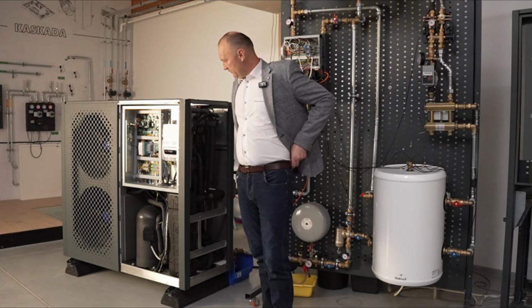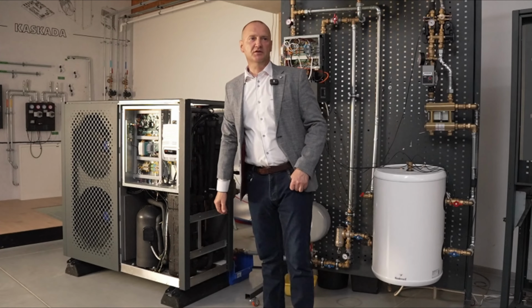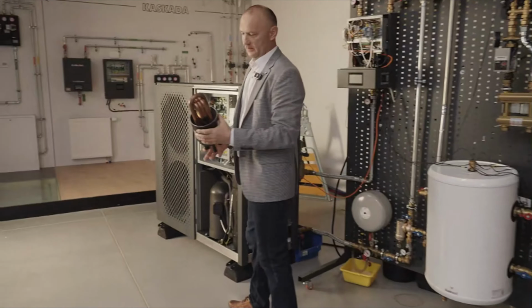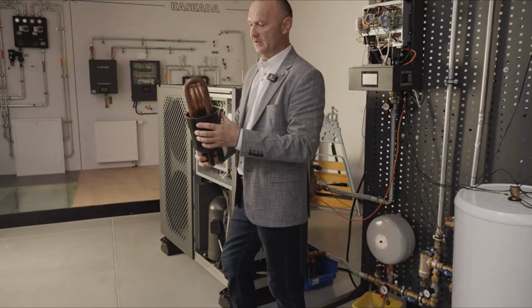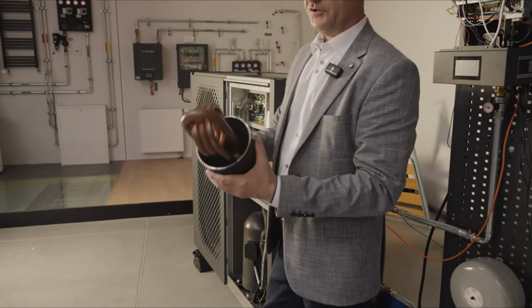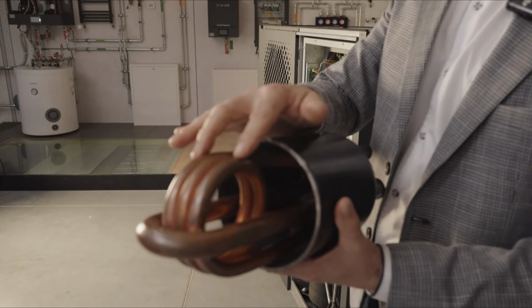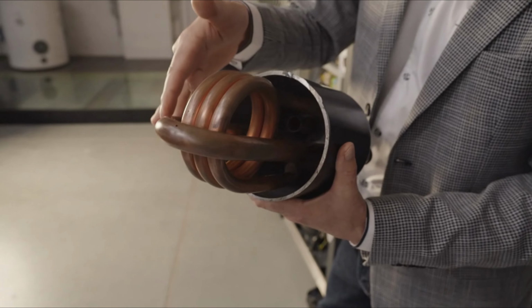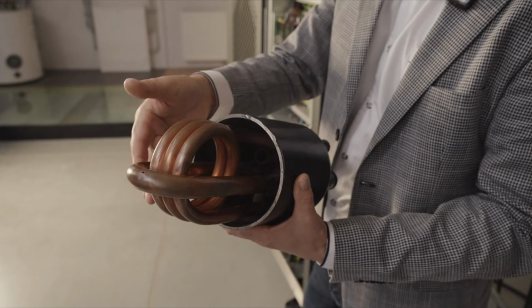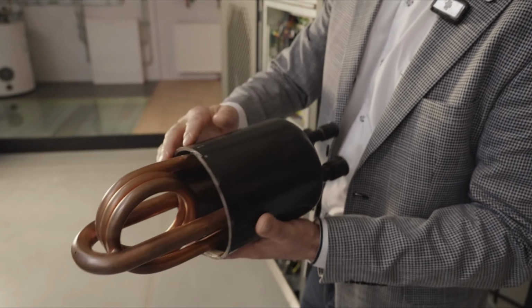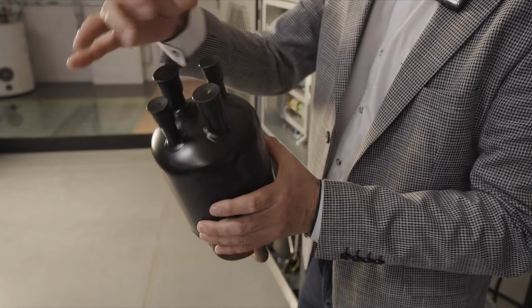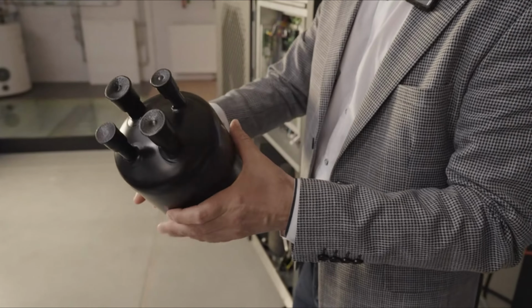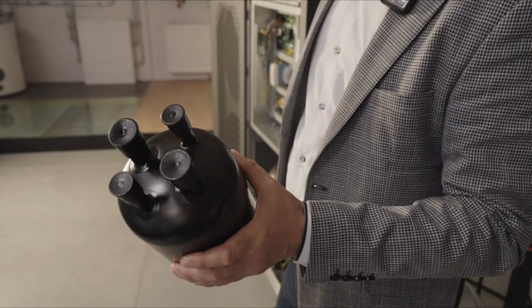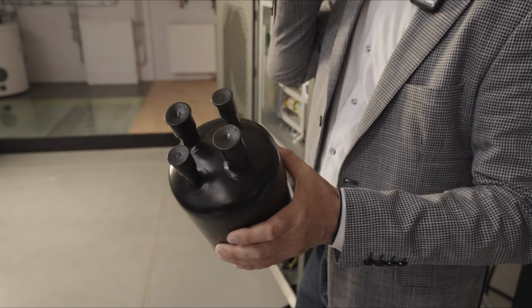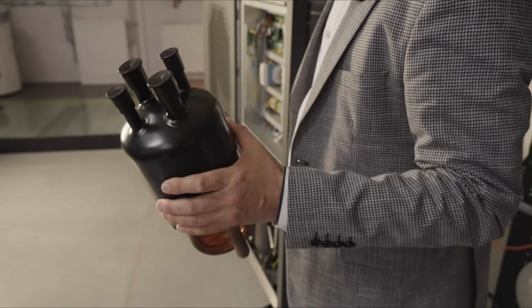We happen to have such a cut-open component here. I can show you how it looks. This is what such a device looks like. So, a standard liquid separator doesn't have this element at all, this coil. In our device, this tube is a separator element. And additionally, it has such a coil. So our separator has not 2, but 4 connection ports. This improves the energy efficiency of the entire process and the entire device.